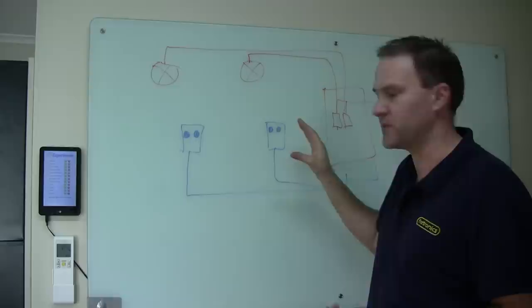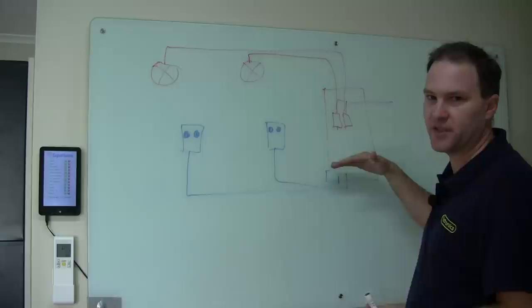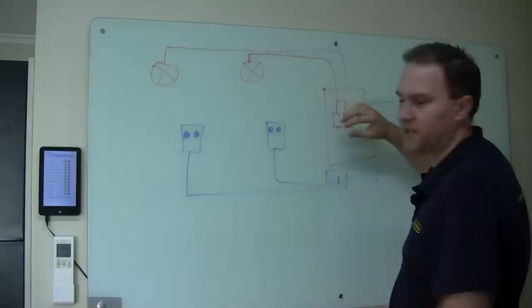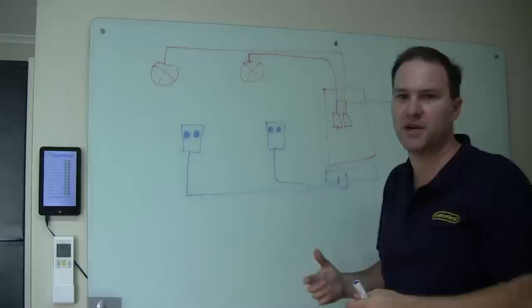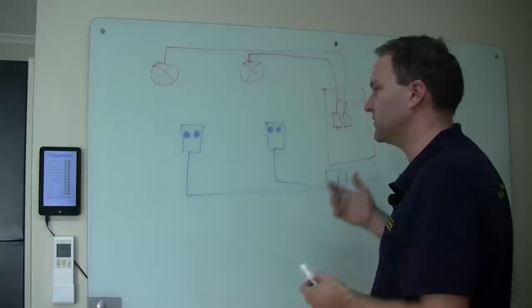So the end result is that what we have is centralized links for all of the lights coming back to a switchboard and we also have centralized links for all of the control surfaces, so the light switches, the buttons coming back to an ethernet switch. Now the interesting bit is what happens between those. So we've got high voltage and low voltage totally isolated. This is logic, it's just messages passing around, it's not actually switching anything directly. This is where all of the loads are controlled, where all the high voltage stuff happens.